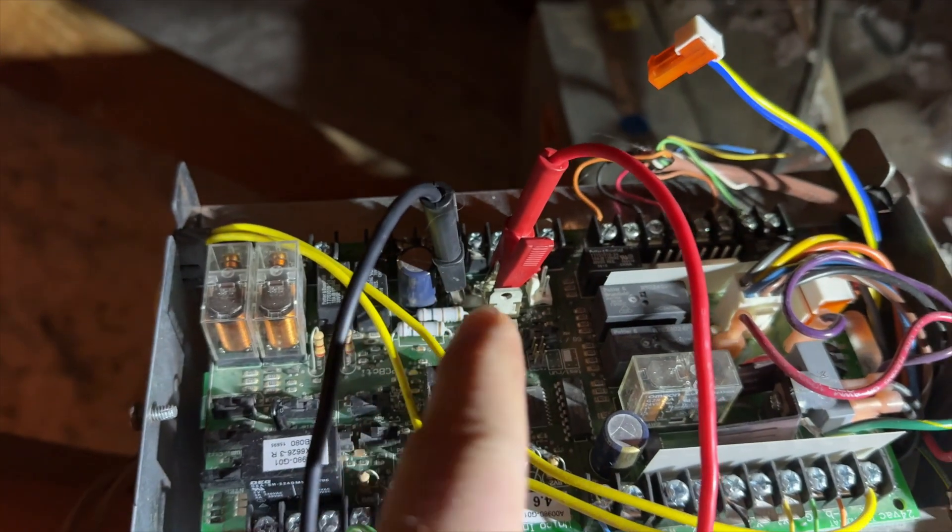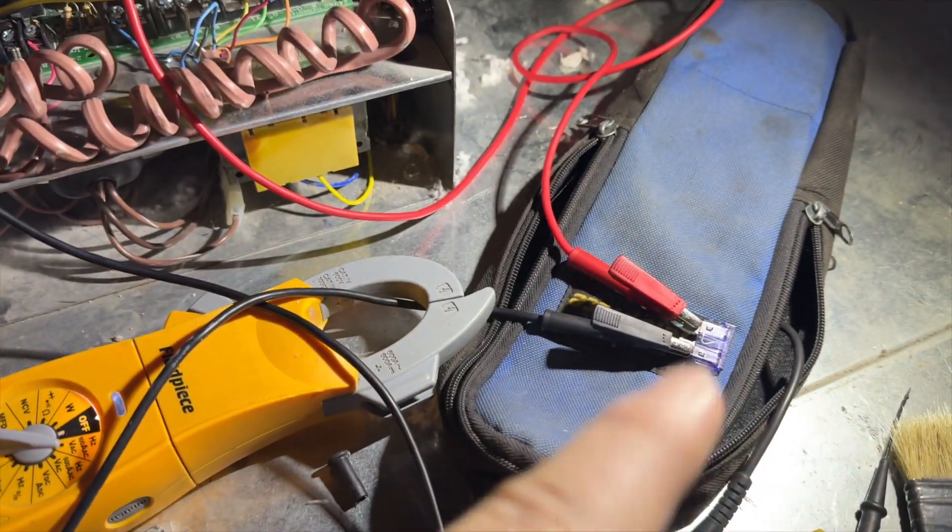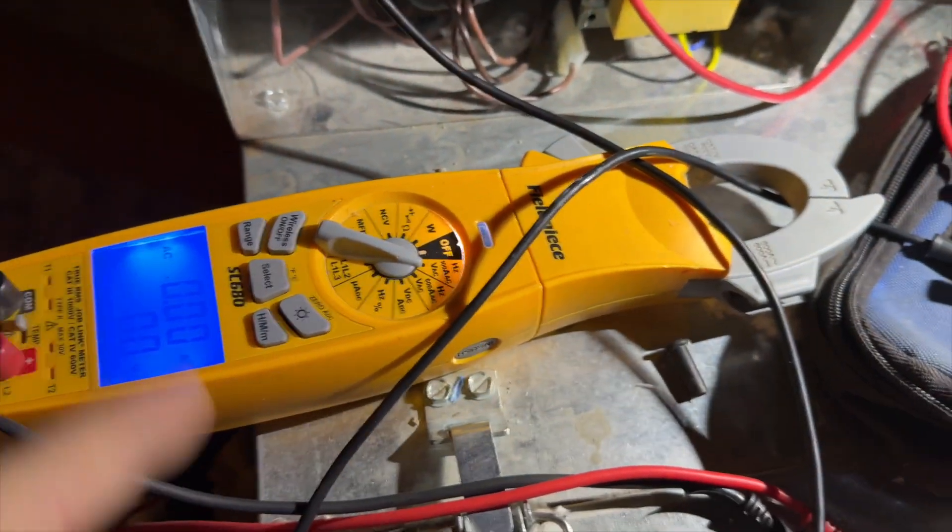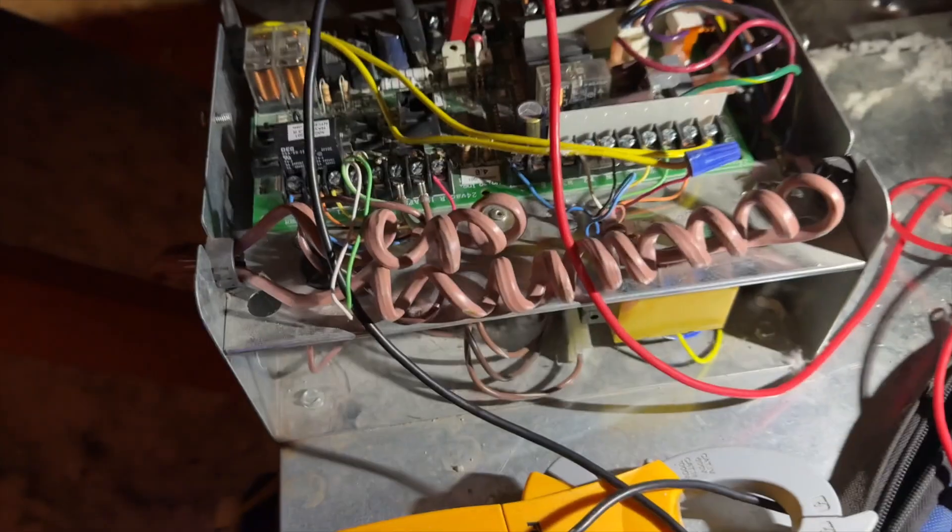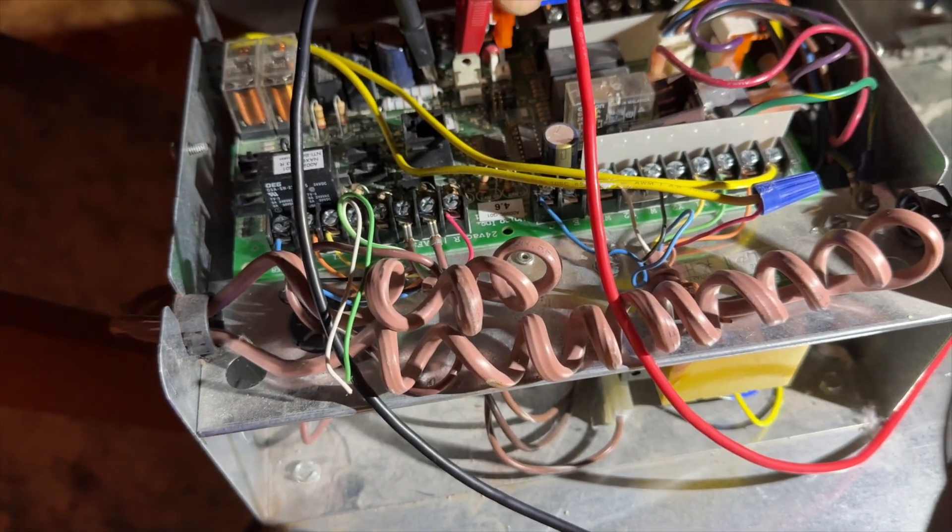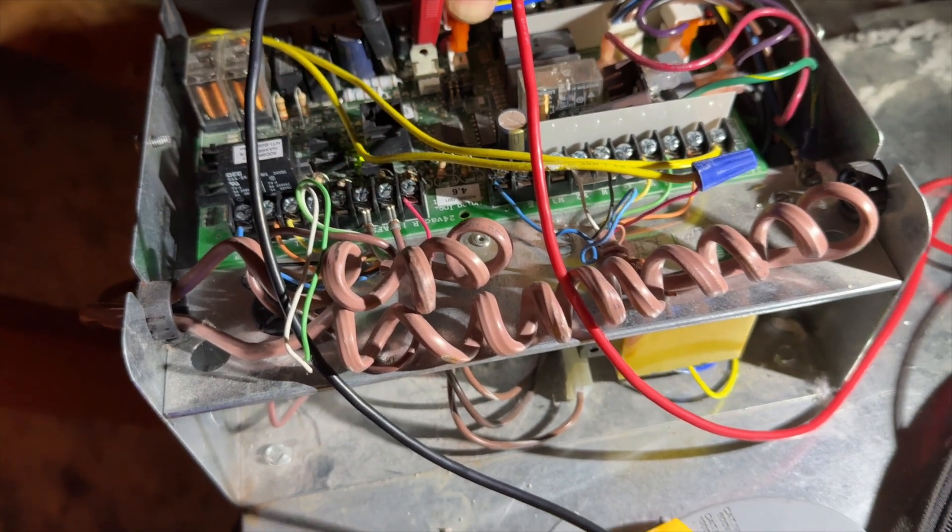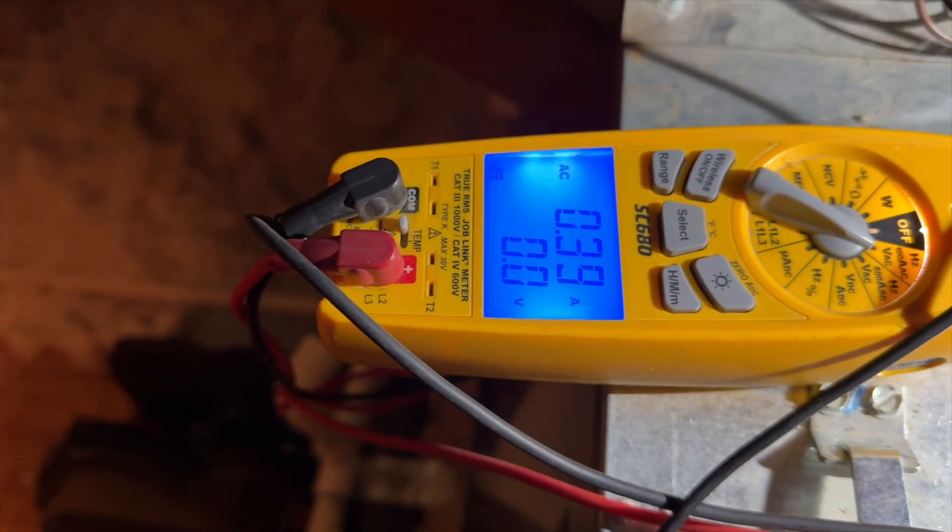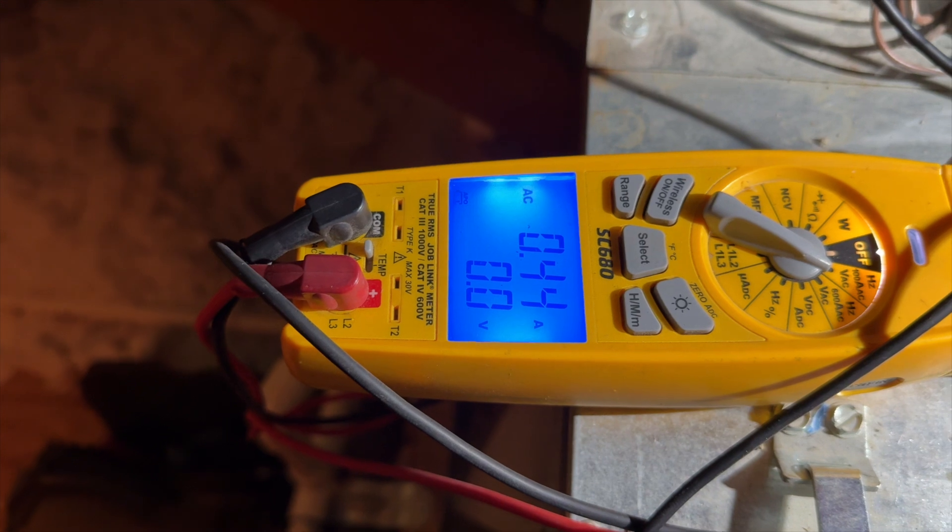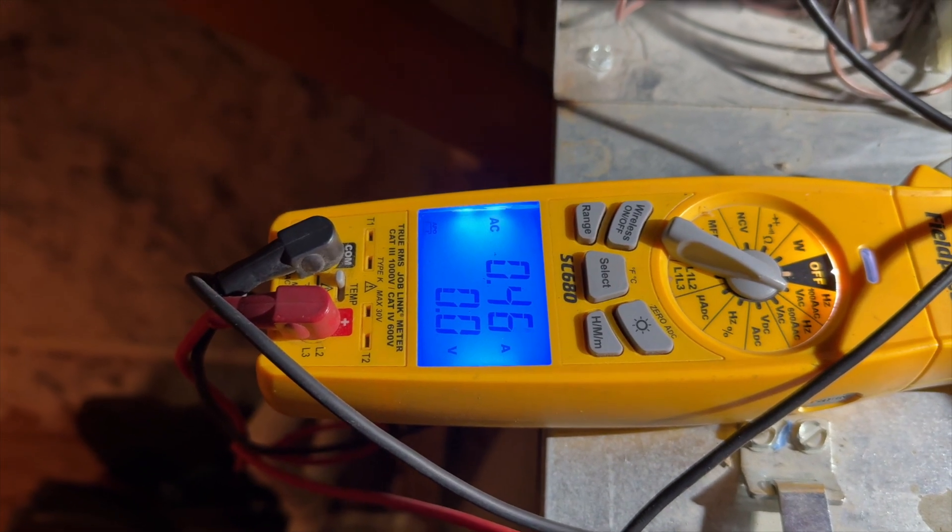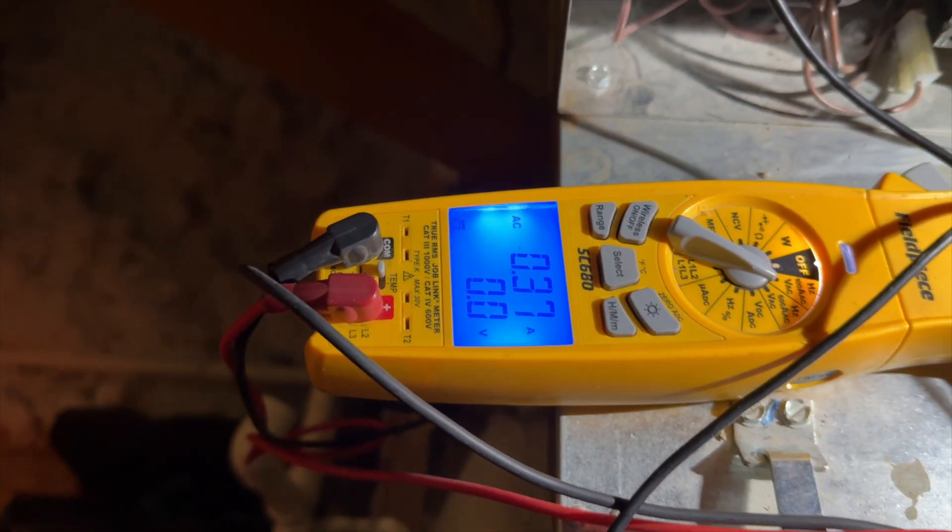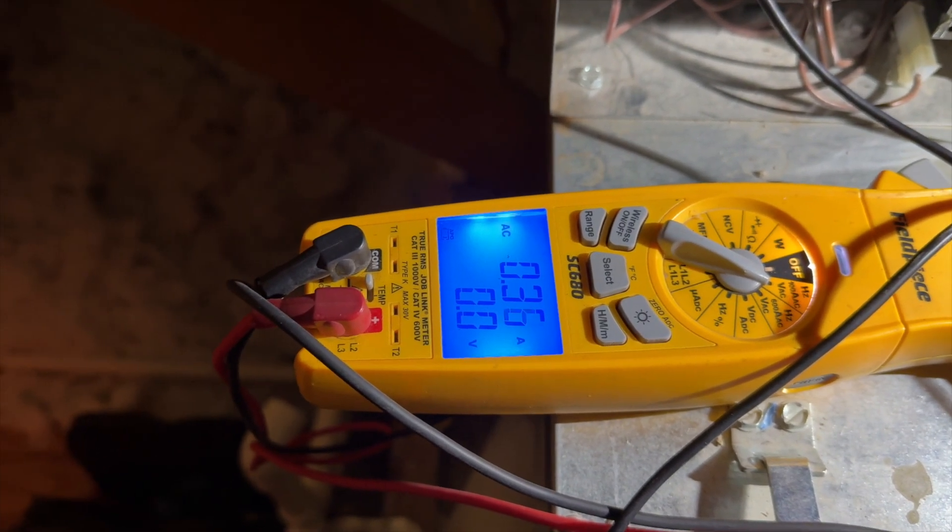What I've done here is I've put my jumper wires on each side of the fuse holder, and then I've clamped on a three amp fuse. The glass one is a two and a half, but I just want to see if it'll work. I got my amp clamp on there, so we'll see what the amp draw is and we'll apply power, 24 volt power. Here we go. Okay, drawing 0.4 amps. Blower motor just kicked on, so we may have just had a bad fuse.